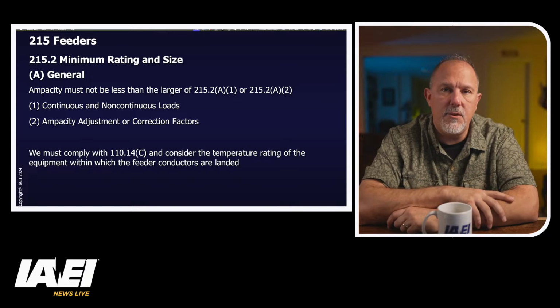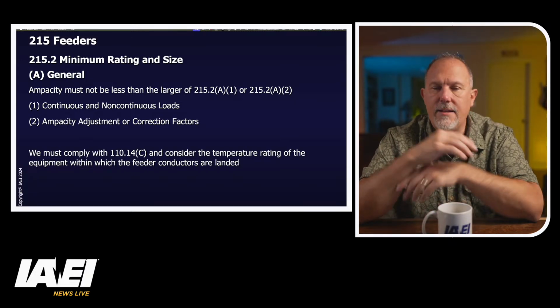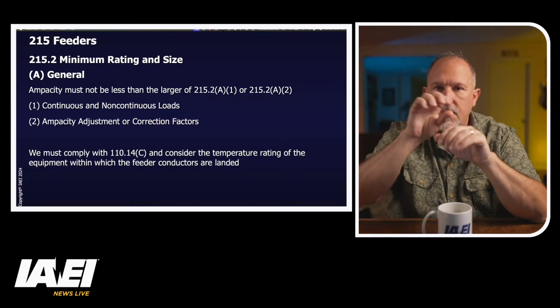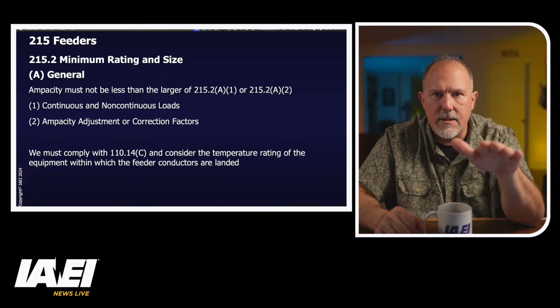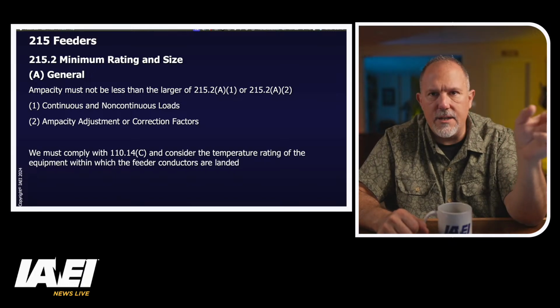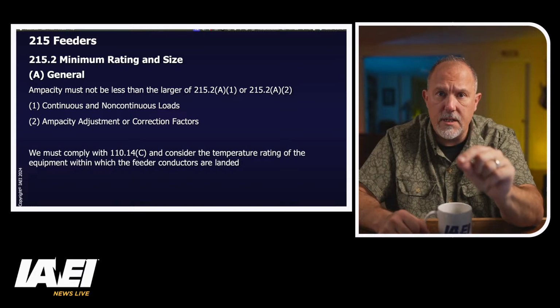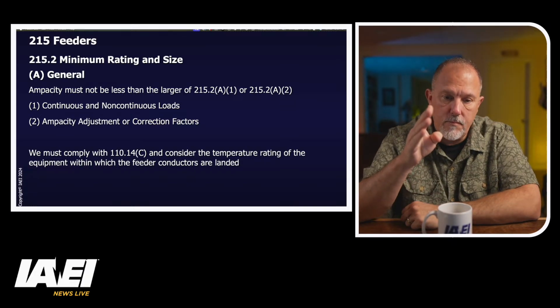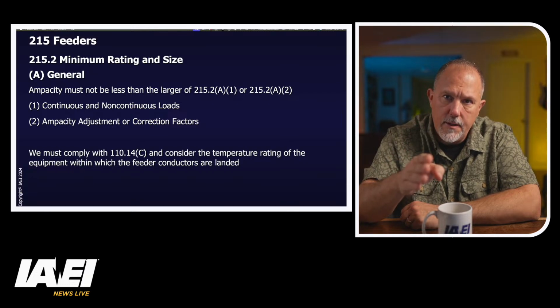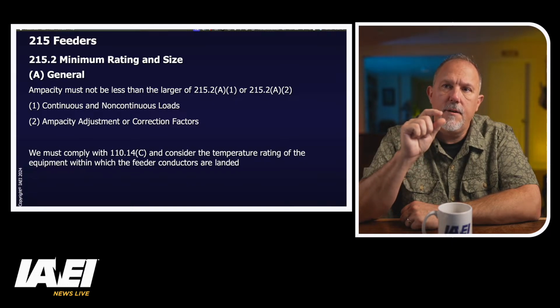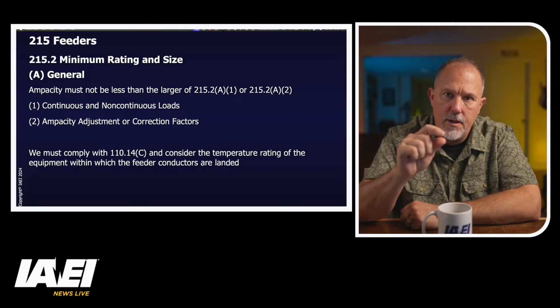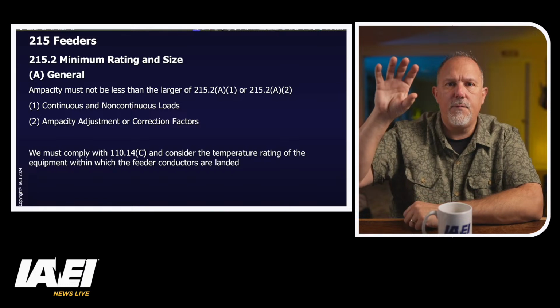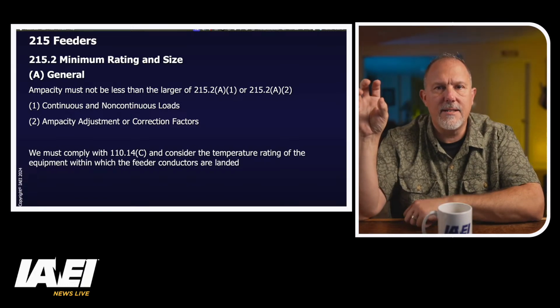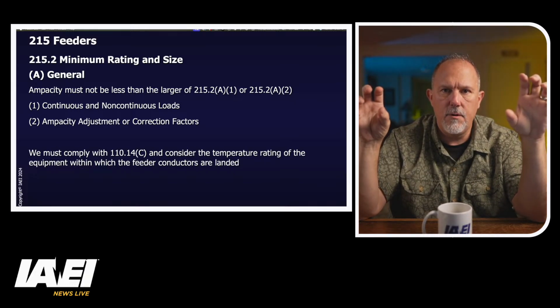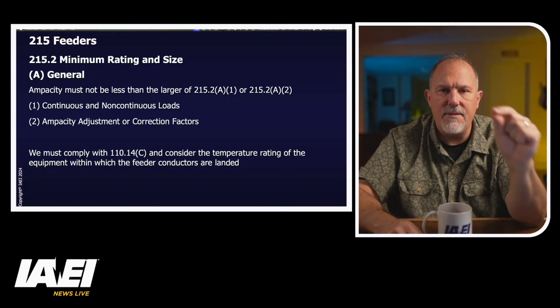So the first step is you take your continuous and non-continuous loads. You do 1.25 times the continuous, and you add the non-continuous. And if that comes up to 150 amps, then you put that over here and you say, okay, I got 150 amps. Then you forget about the continuous loads at 125%, and you simply adjust for the correction factors, which is based upon the conditions of use. Now that would be how many conductors you have in a raceway, and then temperature. So you adjust based upon those conditions of use, and then that tells you the current. Now, if we said it was 150 for A1, and let's say it's 175 for A2, then you need a conductor that can handle 175 amps.